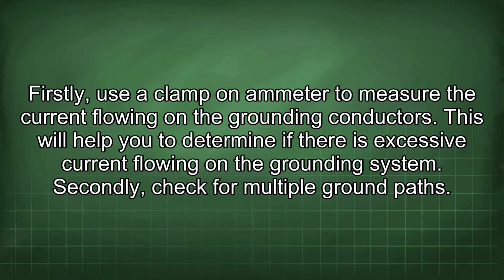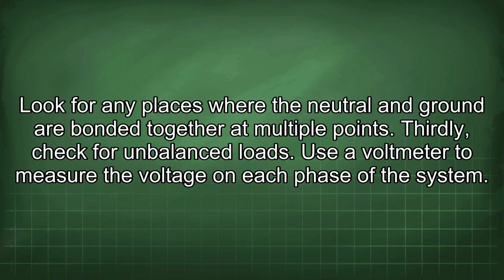Firstly, use a clamp-on ammeter to measure the current flowing on the grounding conductors. This will help you to determine if there is excessive current flowing on the grounding system. Secondly, check for multiple ground paths. Look for any places where the neutral and ground are bonded together at multiple points.